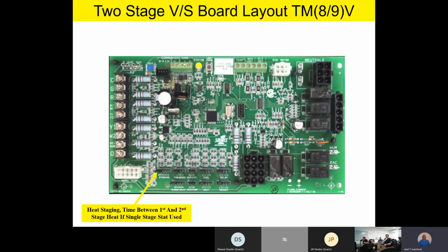The final jumper that we have on our board is what we call a staging jumper. Now remember, if you're stuck with a single stage thermostat, it'd be kind of nice to have some staging function, right? Well, this is actually what this is. This is a staging jumper if you're stuck with a single stage thermostat. So there's going to be some positions on it. It's going to be like 10, 15, 20 minutes and off.